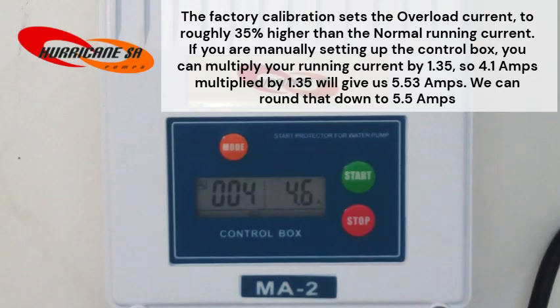The factory calibration sets the overload current to roughly 35% higher than the normal running current. If you are manually setting up the control box, you can multiply your running current by 1.35. So 4.1 amps multiplied by 1.35 will give us 5.53 amps. We can round that down to 5.5 amps.